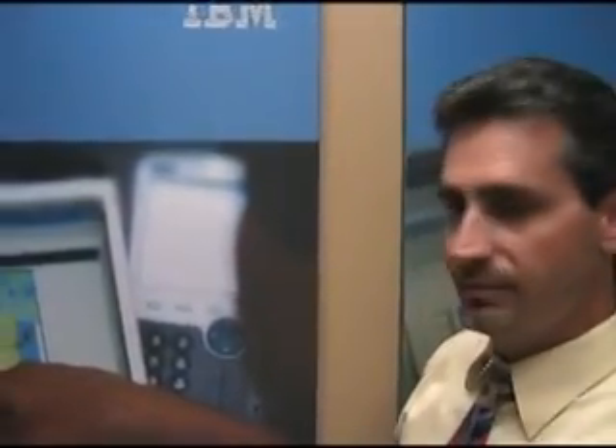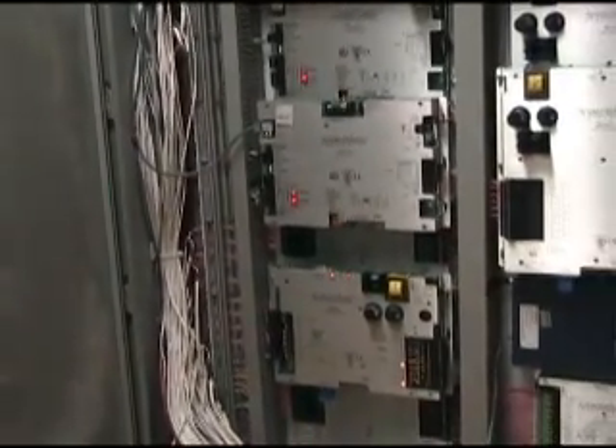Now the picture behind you is actually a thermal map of this data center, and all the green points on there are sensors, is that right? Absolutely. So the first step was that we instrumented the lab with over 200 sensors. Then we connected them so they can all talk together. We aggregated them into one focal point in a programmable logic controller, and now we're applying intelligence on that — pulling information off that aggregation point to figure out what's valuable to help us optimize the data center efficiency in terms of energy, power, and cooling.